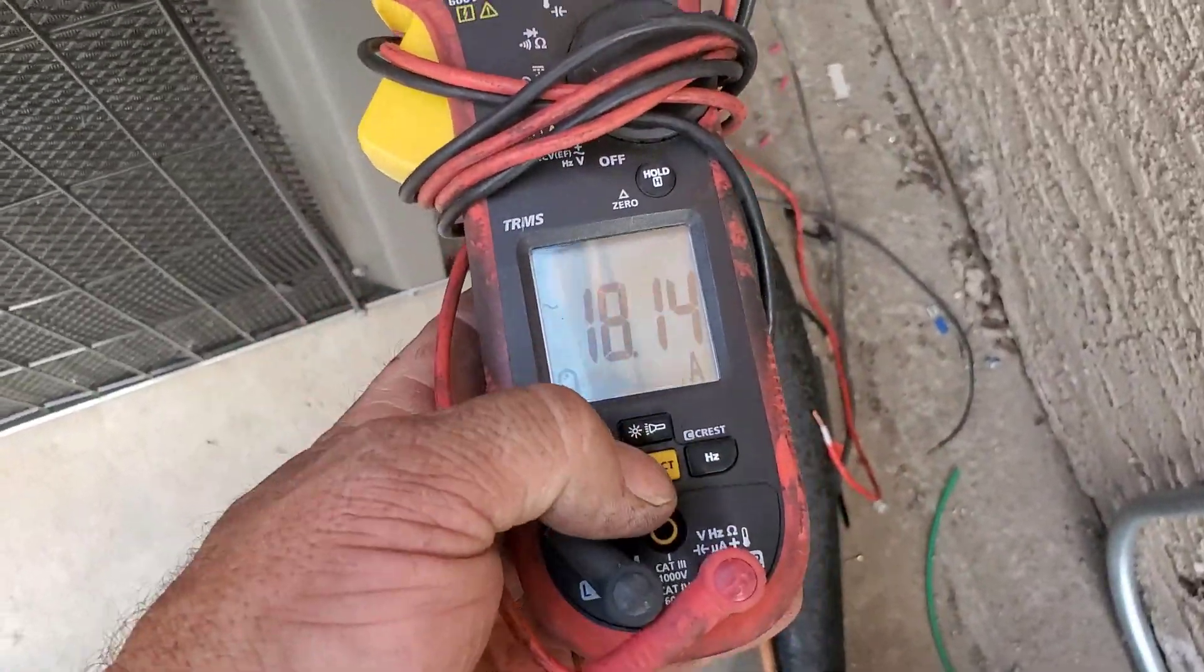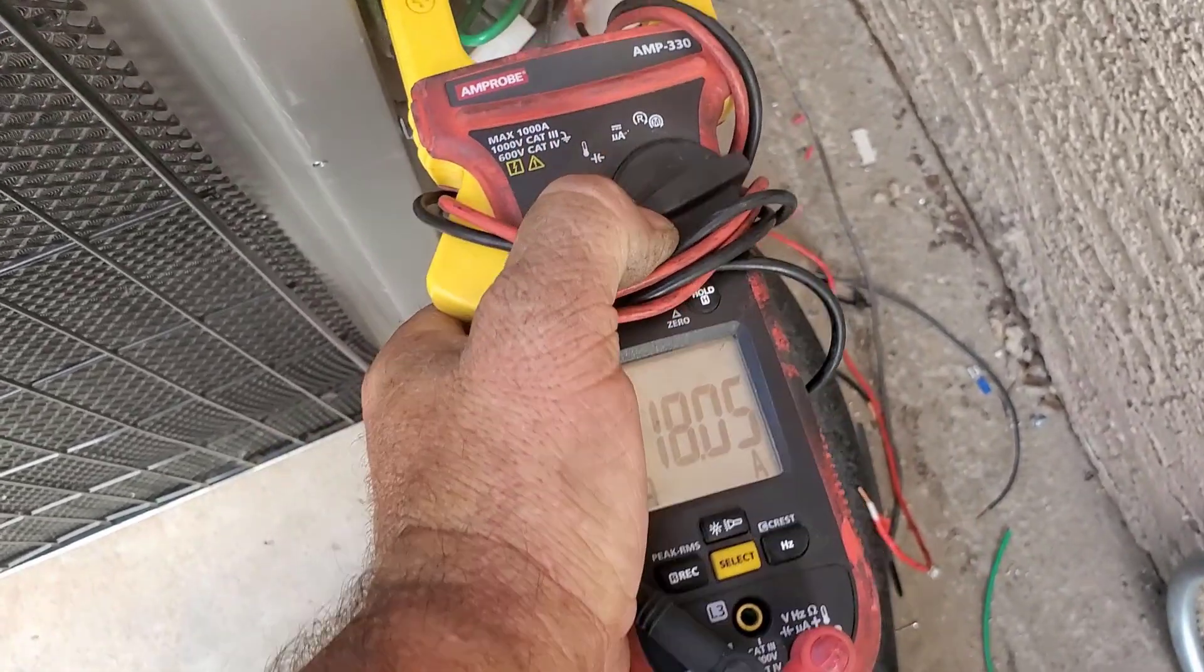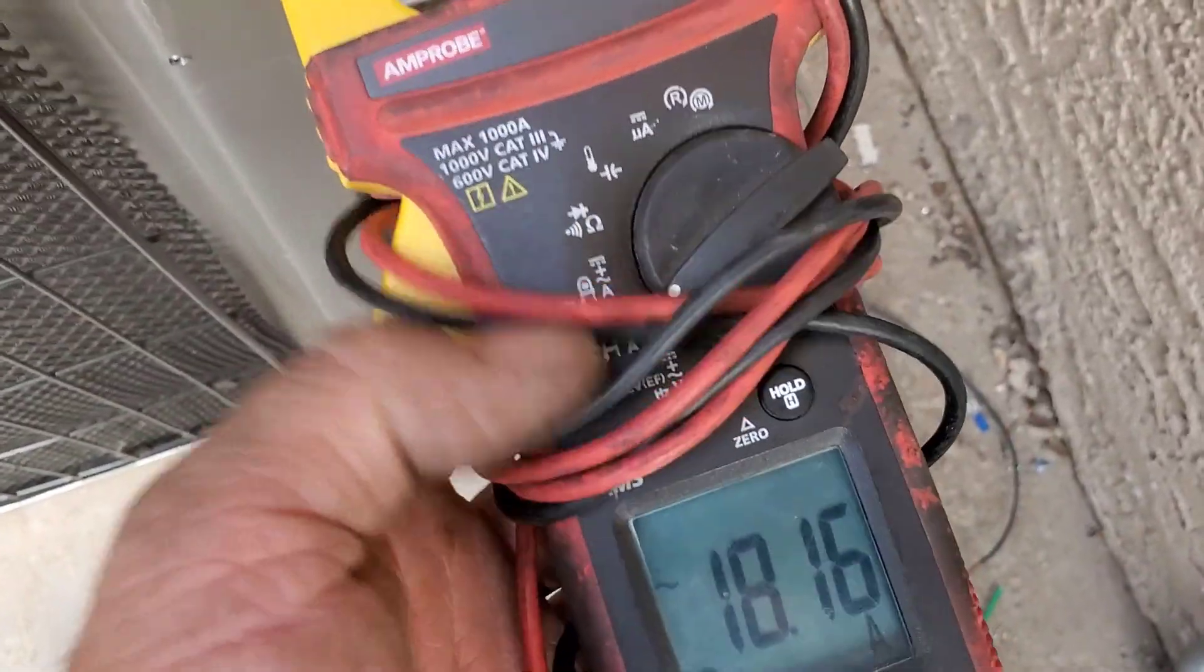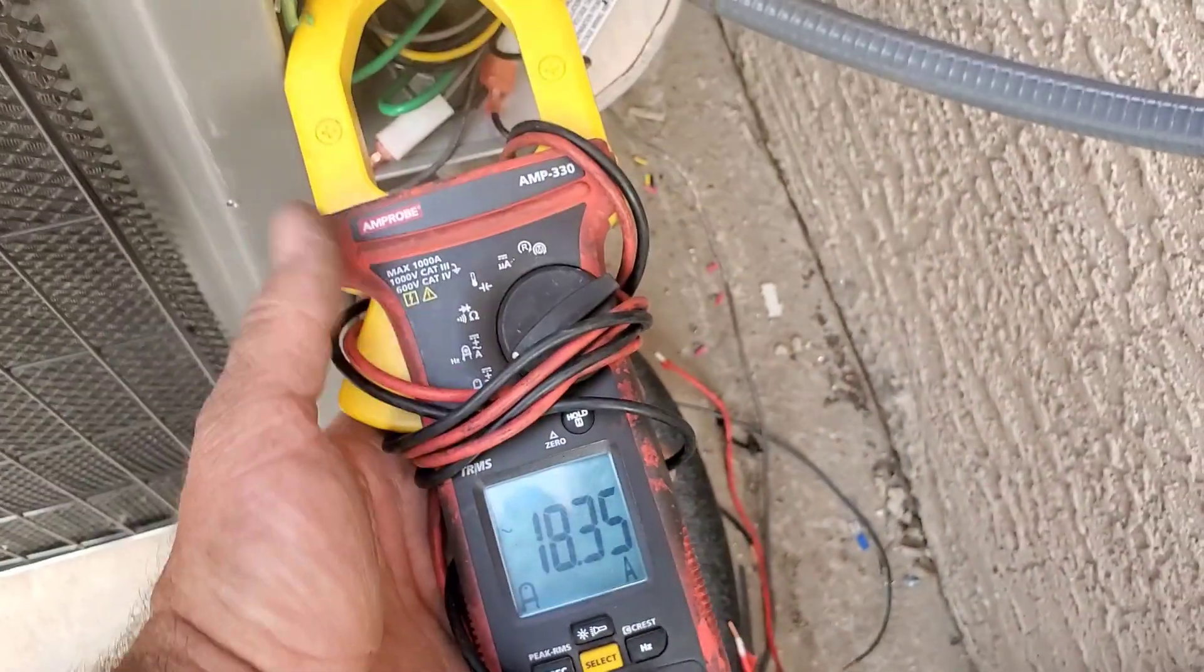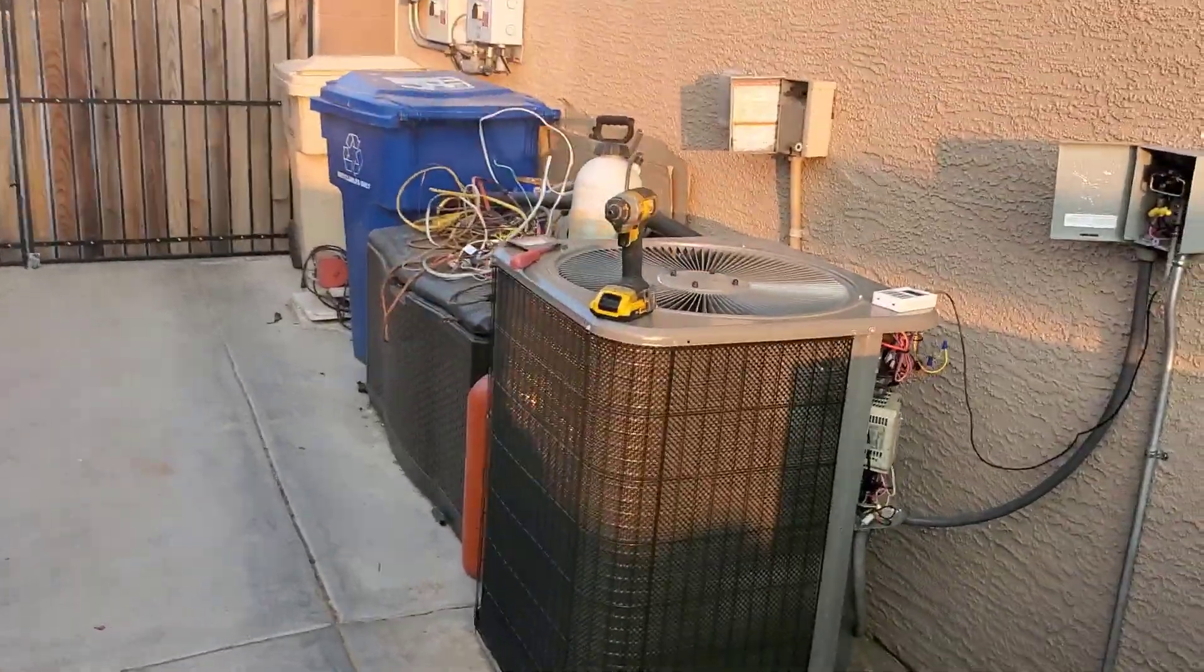Right now 18 amps, so it's cooled off a little bit. DC, I don't know what that means - DC plus AC, whatever that means, 18.3, or go back to that 18.2. Doesn't matter if we put it on the high, it's got two settings. One is for like it shows you putting the lead right there in that little pimple right there - I think that's for low amps. The compressor is running just like it should and the amps output is just like it should be.